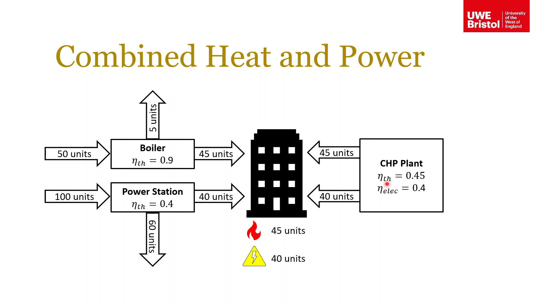The lower thermal efficiency is reasonable because the heat is lower grade — you're taking heat from the exhaust. With 45 units of thermal energy at 45 percent efficiency and 40 units of electrical energy at 40 percent efficiency, we need to put in 100 units of energy into the CHP plant. We're getting 85 units out in total, so we're rejecting 15 units.